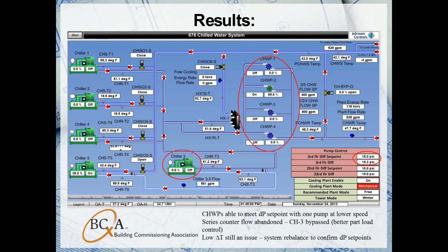That's why you can see now that we've isolated that valve, we're able to meet our differential pressure set point on the third floor here, and we're able to do it with one pump at part speed.